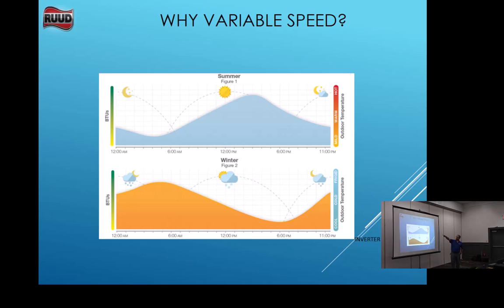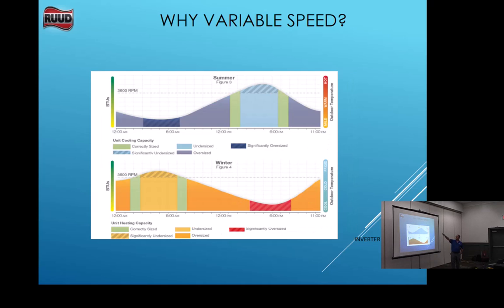With our single speed fixed compressor running at 3,600 RPMs right here, this is where we run at. So we're running at 3,600 RPMs even though we're down here at these low temperatures during the day. Okay. With our full variable, though, once we get up here, then we can only reach so much capacity with our 3,600 RPM compressor. With our fully variable speed compressor, we can go up to that 120 so we can meet more of a demand.